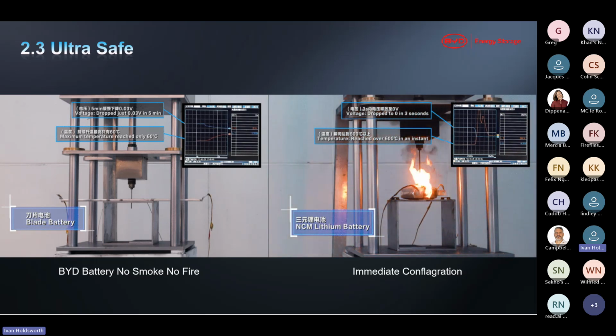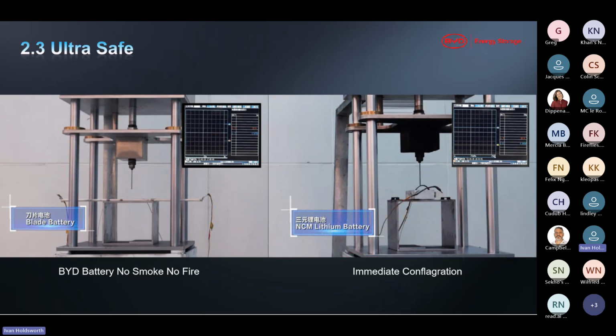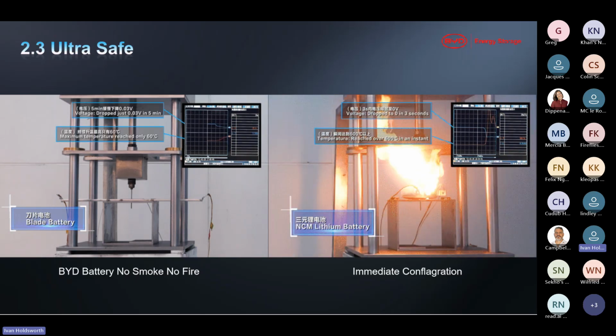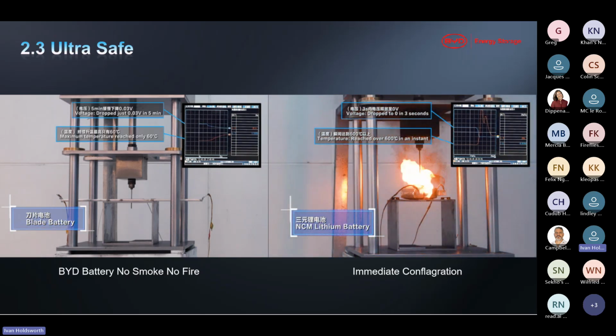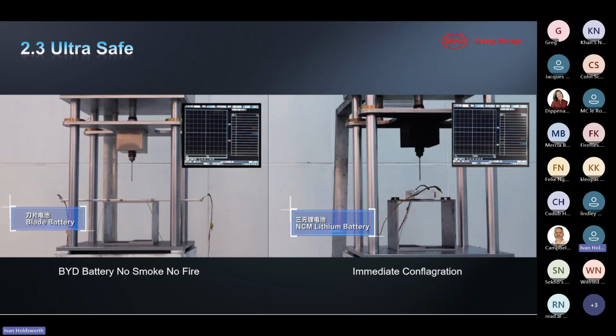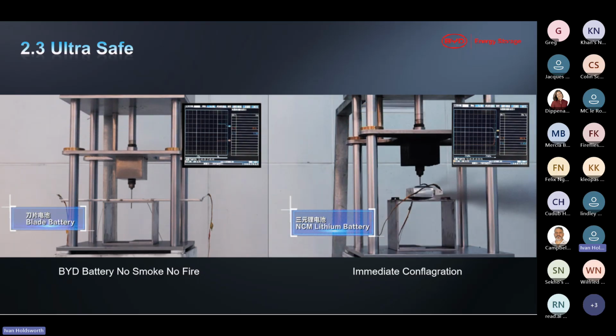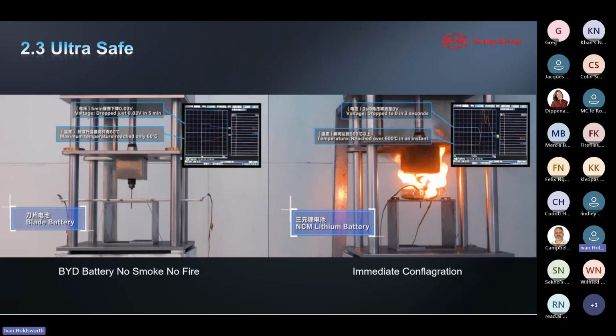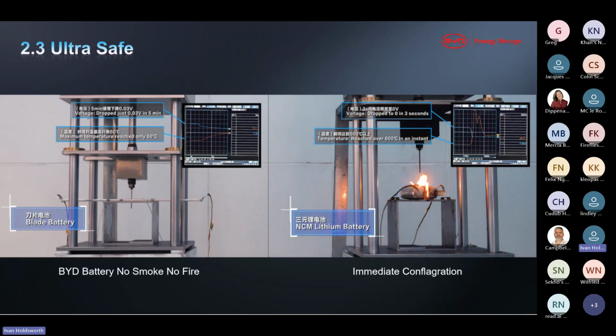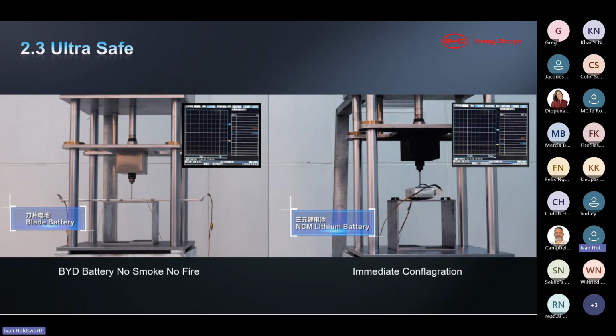And here we can see the NMC doesn't do so well. So what happens is there's two sources of heat. One source will be the self-discharge of the energy in the battery into itself and into the electrolyte, and two, any combustion, external combustion that happens. And NMC has a runaway effect, so it's not generally a good idea to use NMC cells indoors.